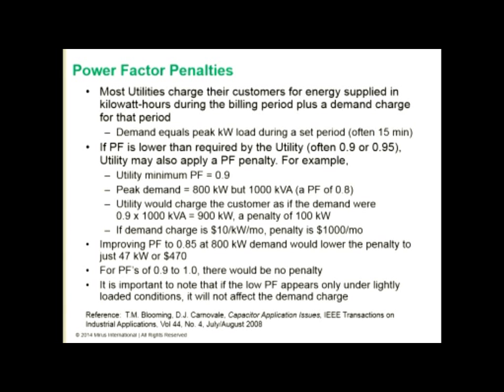If power factor is lower than required by the utility, often 0.9 or 0.95, then the utility may also apply a power factor penalty. An example of this would be if the utility had 0.9 as their minimum allowed power factor, and the peak demand happened to be 800 kilowatts, but the apparent power was 1,000 kVA. This would indicate a power factor of 0.8.